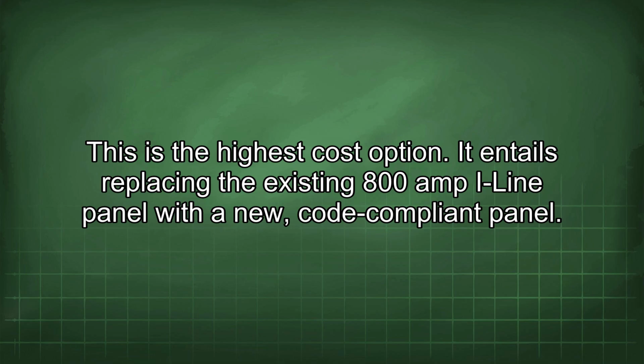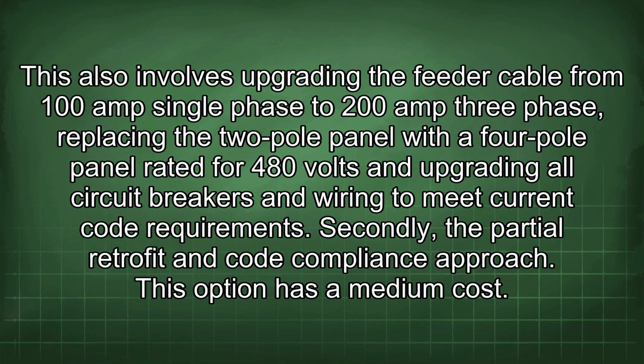It entails replacing the existing 800 amp I-Line panel with a new, code-compliant panel. This also involves upgrading the feeder cable from 100 amp single-phase to 200 amp three-phase, replacing the two-pole panel with a four-pole panel rated for 480 volts, and upgrading all circuit breakers and wiring to meet current code requirements.